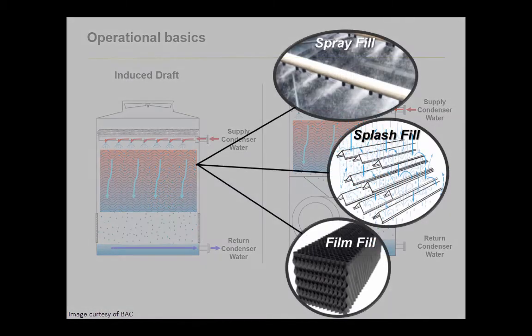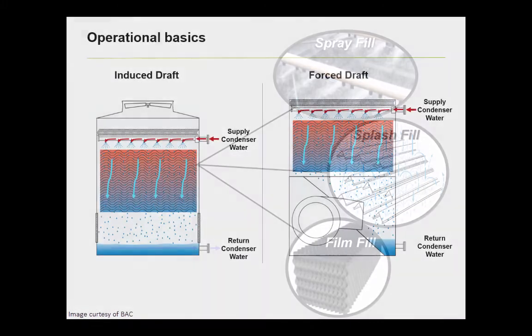There are several common types of fill as you can see: spray, splash, and film. Second, and in parallel, air is being pulled — as with an induced draft tower — or pushed with a forced draft tower via a fan-motor combination across the fill. After the air and water interact, the now warmer, more humid air is rejected out of the cooling tower to the atmosphere, and the resulting cooler water collects at the bottom of the cooling tower before it's sent back to the building.